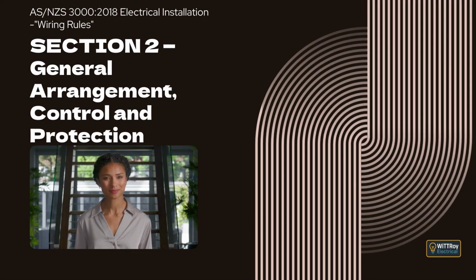Clause 2.6.2.3, Protection against initiation of fire. Type S RCDs with rated residual currents from 100 mA to 300 mA may be used to reduce the risk of fire caused by leakage across damaged insulation. They operate more slowly and provide a different kind of protection, but are not a substitute for the 30 mA devices needed for shock protection.